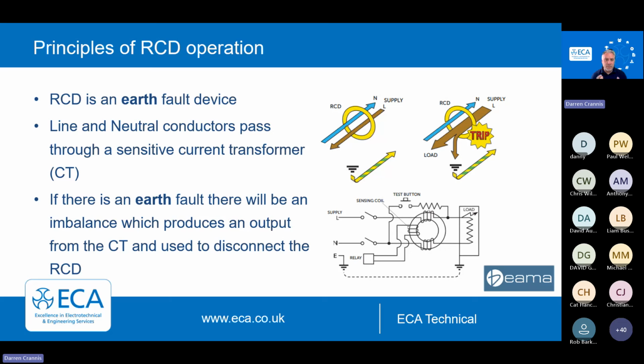Now, the real difficulties of late with RCDs is where we hear about this blinding effect. If you look at the image at the moment, kindly given to us by BEAMA, you'll see this round ferrous coil. And this DC phenomenon we're on about, that blinding, is all about that coil being saturated with the effects of the DC. And that affects the ability for that tripping coil to work. So when we talk about DC blinding, it's that little tiny coil, and it just becomes stunned. It becomes magnetized in one way, and it's unable to detect that imbalance.